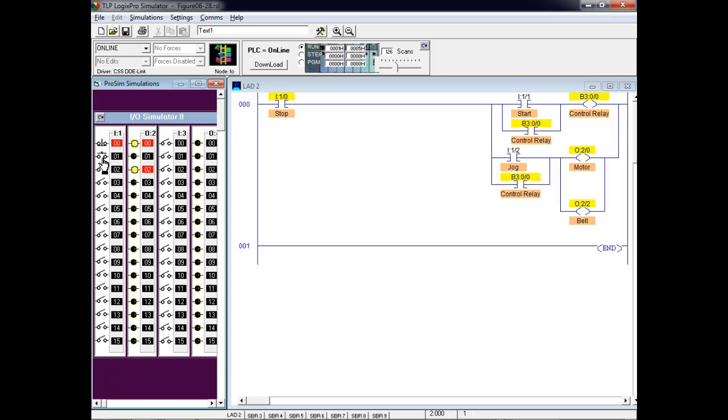Yeah, the jog will work whether or not the on switch is on or not. Well, the switch will work, but it doesn't mean anything because we've got it in run. So if the motor's running, then jogging makes no difference, right? See the switch actually go into play. If I stop it, then I can come down here and then we can jog the motor. But with the motor running, you can't jog the motor. But see, that's a major issue.